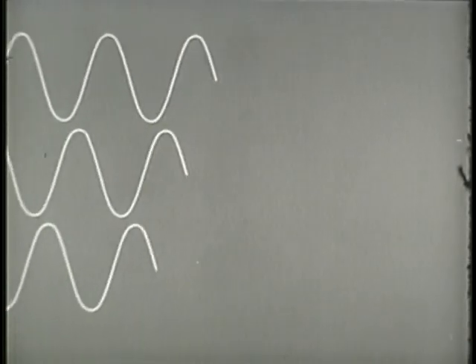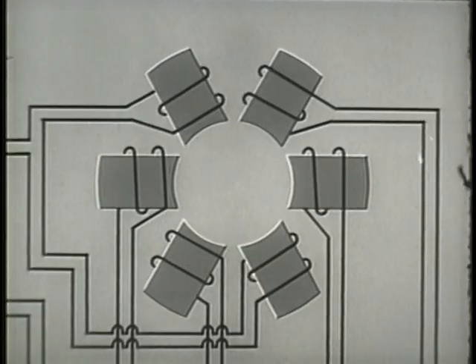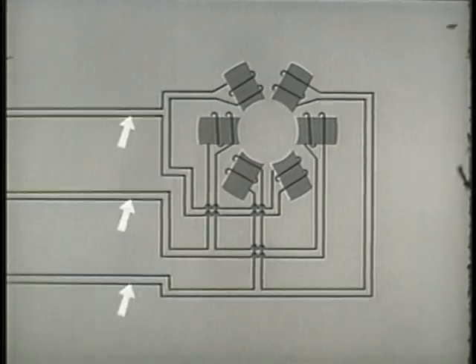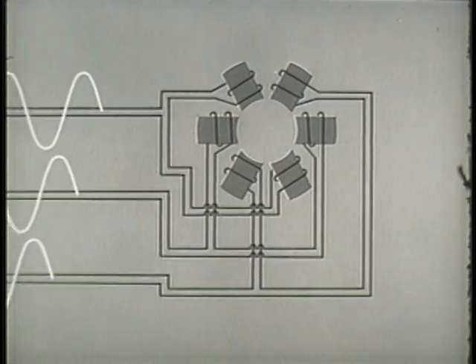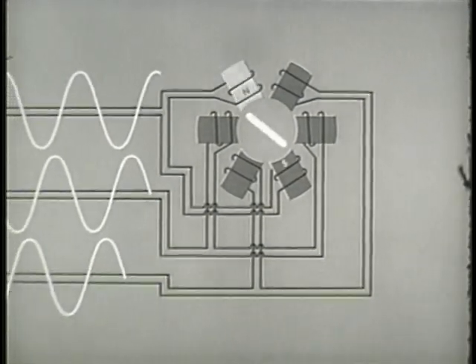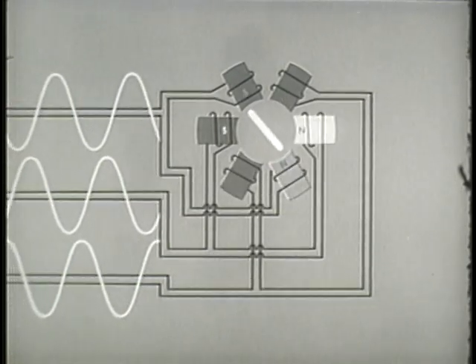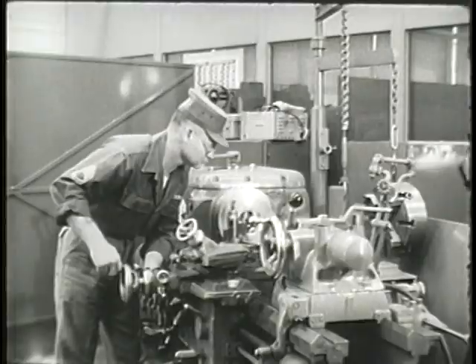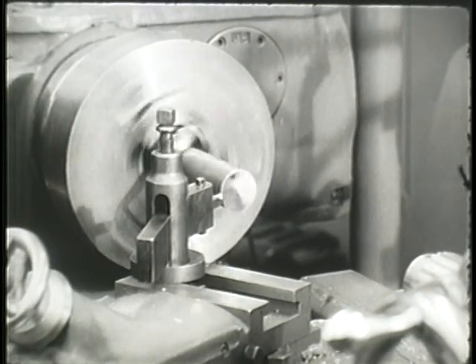We saw earlier how three voltages 120 degrees out of phase were generated. This voltage can be used to rotate the field electrically. Six magnets set in a circular arrangement represent the field of a three-phase induction motor. These three pairs of conductors, one pair for each AC phase, supply the field. Because of the time difference in the three phases, the poles will be energized in successive order, thus rotating the field electrically. Since the rotating field is cutting the rotor, it will rotate in the same direction as the rotating field but at a slightly slower speed.